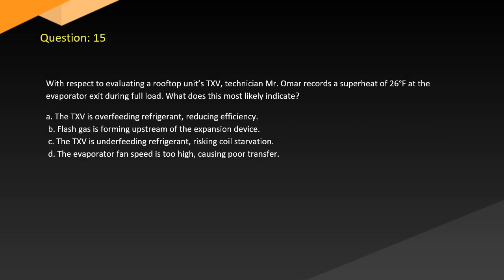Question 15. With respect to evaluating a rooftop unit's TXV, technician Mr. Omar records superheat of 26 degrees at the evaporator exit during full load. What does this most likely indicate? A. The TXV is overfeeding refrigerant, reducing efficiency. B. Flash gas is forming upstream of the expansion device. C. The TXV is underfeeding refrigerant, risking coil starvation. D. The evaporator fan speed is too high, causing poor heat transfer.